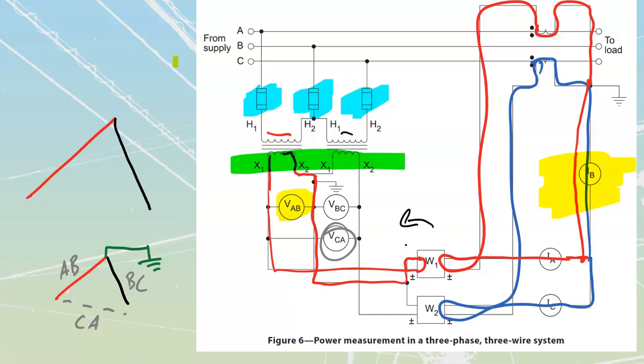But if for whatever reason you can't fix that power factor, then flip around one of these two coils—either flip the connections on these two, or flip the connections on the other two—and that would bring these things together. But you'd have to subtract the reading of the one that was going downscale, which you flipped around, from the other. Once again, don't use that formula unless you know for a fact it's a balanced type of load.